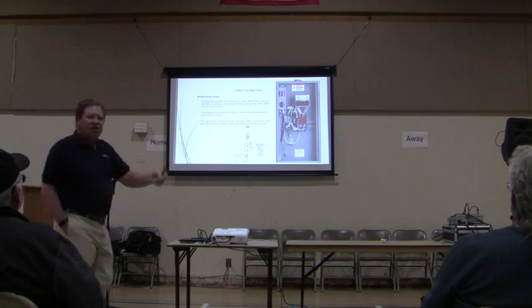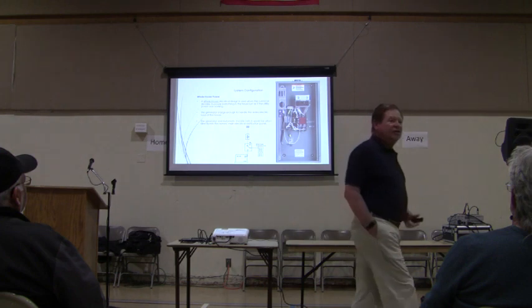So what happens on loss of power? I have a solenoid switch here, and this will transfer over to generator power once generator power becomes available, and transfer back to utility power when utility power has come back on and proven to be stable. A transfer switch is a transfer switch - its purpose is to give you access to electrical circuits either under utility power or generator power, but not both at the same time.